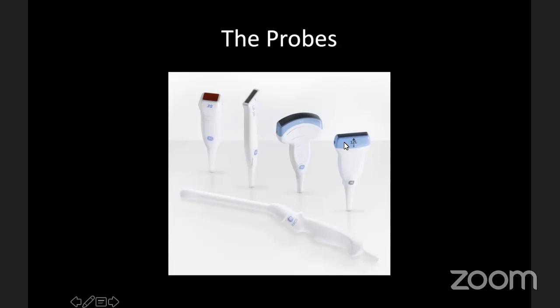We'll start on the right side here. This is called the linear probe, and it has a high frequency ultrasound beam. It doesn't have deeper penetration because of the high frequency, which is why it gives you a very detailed picture of superficial structures.